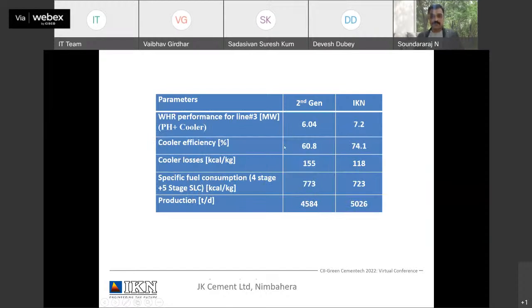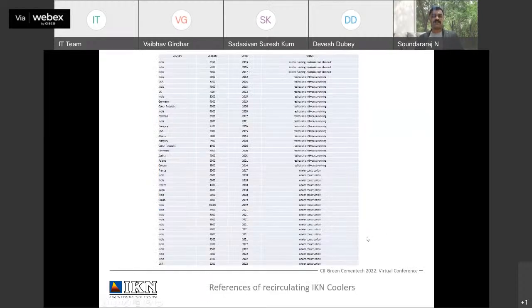Looking at the WHRS performance, earlier with the second generation hybrid cooler it was 6 megawatt, and after IKN with the hot air recirculation it becomes 7.2. The efficiency improved by 14%, cooler losses came down by 35 kilocalories, and heat consumption came down by 50 kilocalories with the help of burner modification also. Production has gone up by 500 tons more, and the kiln is now operating at 6,500 with the upgraded preheater and still the same cooler, without any additional capex on the cooler. These are some references of hot air recirculating IKN coolers, and most of them are from India: Ultratech Lines, Wonder Cement, Birla Corporations and other cement groups, and Dalmia as well.